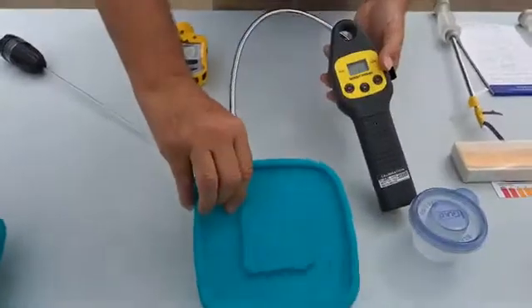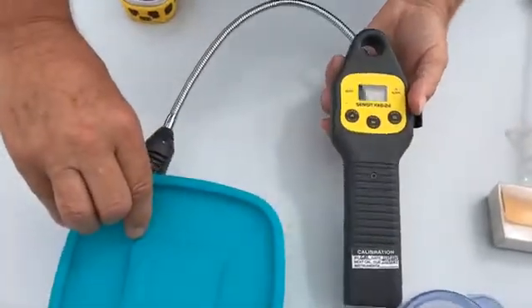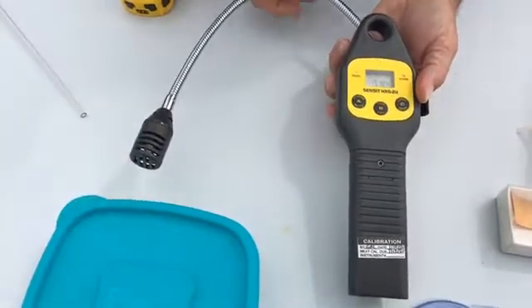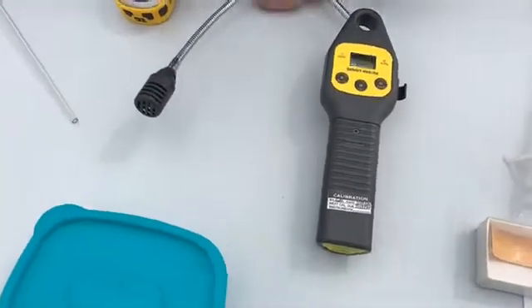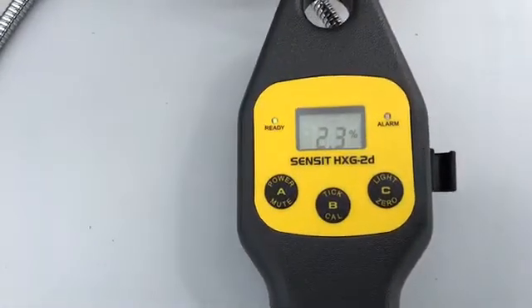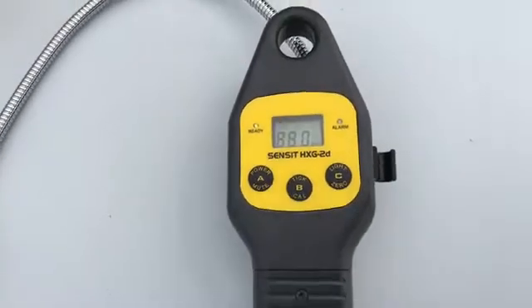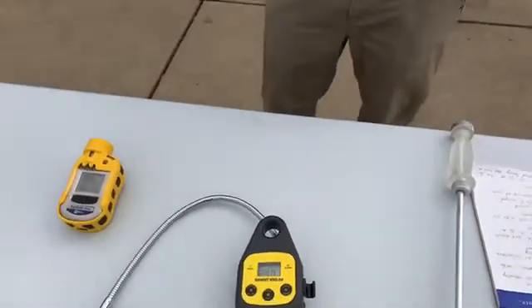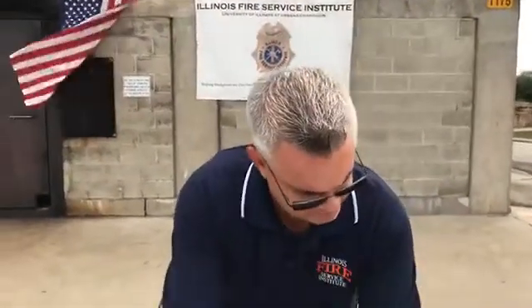What I'm going to do now is I'm going to use a real chemical, and I'm going to activate the monitor so you can see how quickly it responds to a chemical. Use this bowl right here. As you can see, we've already jumped up to the percentage level of the monitor because it picked up the flammable product inside that bowl very, very quickly. This monitor is great. It's a very fast reacting semiconductor sensor in there. It's excellent for this type of operation, excellent for basic Fireground monitoring, excellent for unknown products because it has that advantage of the speed as well as the difference in parts per million and percent by volume. So it's a great, great instrument for that.